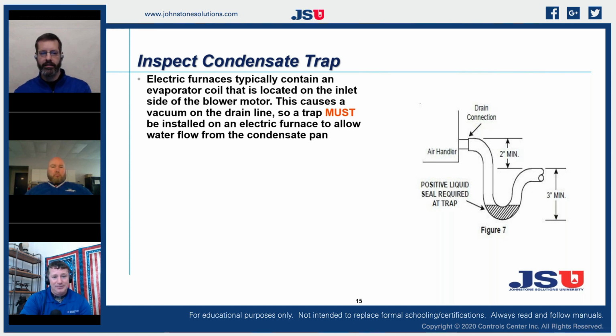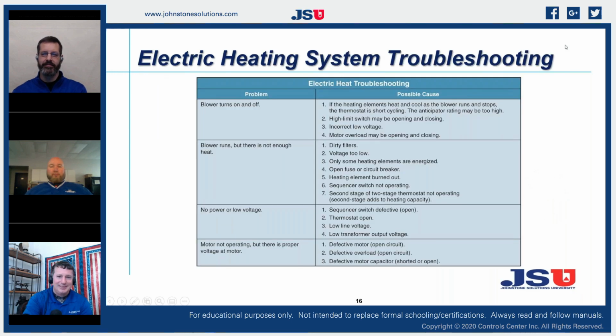For your condensate line, what I'm finding is that companies that don't do that, or companies that put caps on top of that, I get enough back pressure that I suck all of that water out and I lose my pressure on my front cover pressure switch. So it's important to see what these installation manuals say. Don't rely on what you have done in the past. Rely on what's between page 5 and 9 of our installation manual on proper condensate traps on installations. So very important.